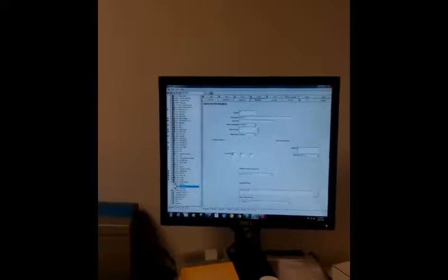ISO code, you're looking at, if I leave it at 21, like that, 21 for 4, 18 for 6, and 15 for 14. Size in microns. It is like what we use when we operate the LaserNet. Is it right? It is. You can select the ISO code, or leave it as default.